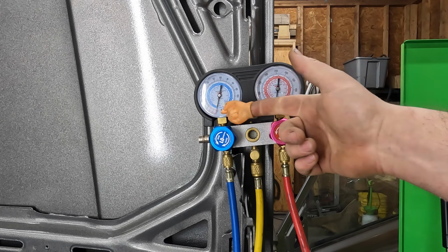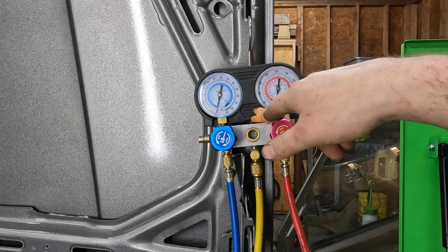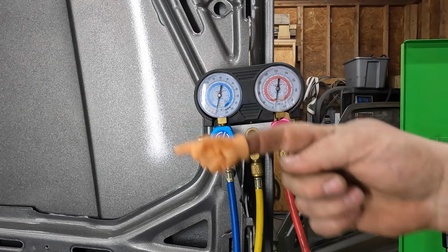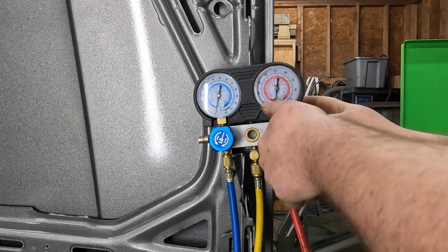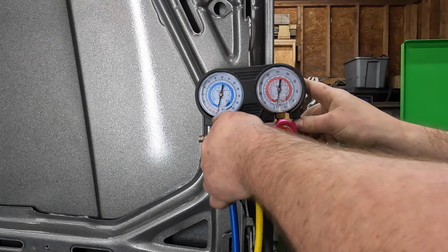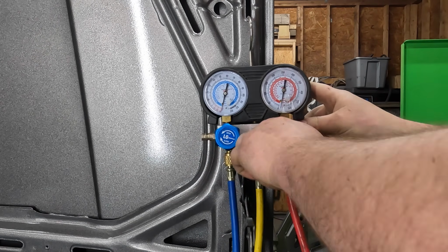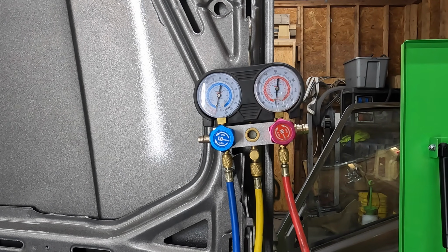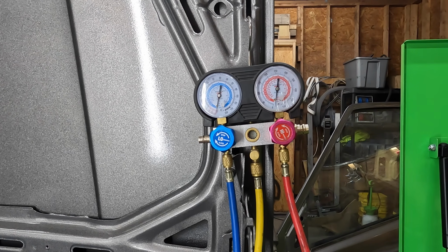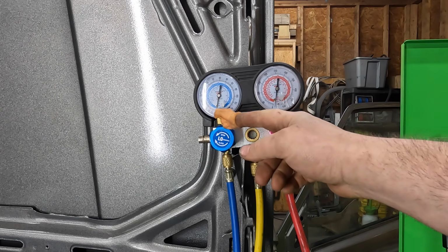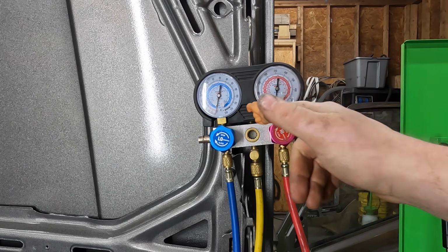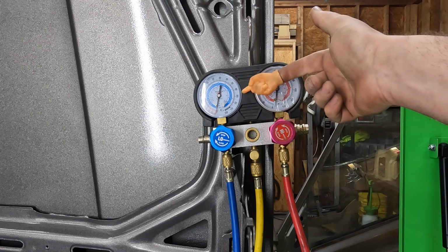So it's now been about 2 hours. We still got a vacuum. Now to leak check it, all we have to do is cut the system off from the vacuum pump. So we'll close these valves and cut the pump off. And we'll see what the needles do. And they didn't immediately fall off to zero, so that's promising. We'll leave it sit like that for a few hours to see where we're at.